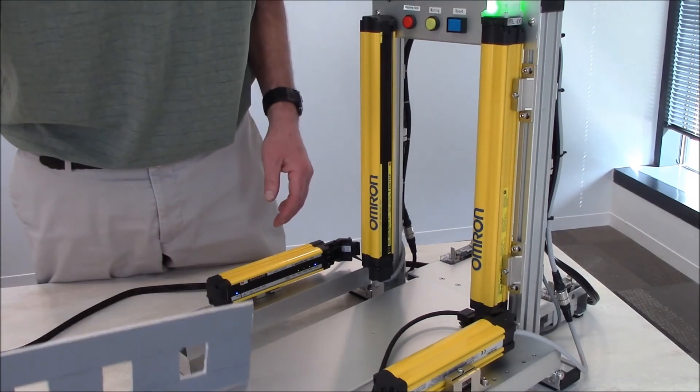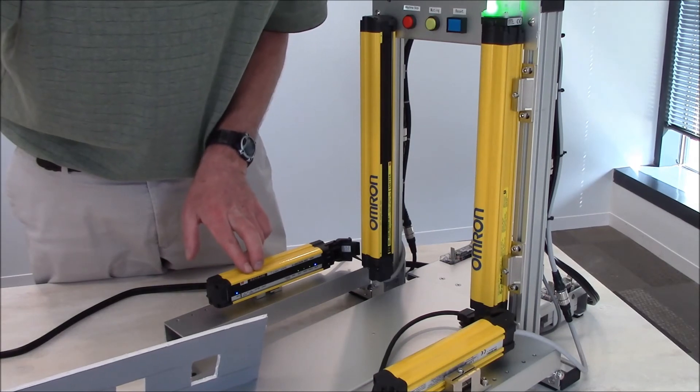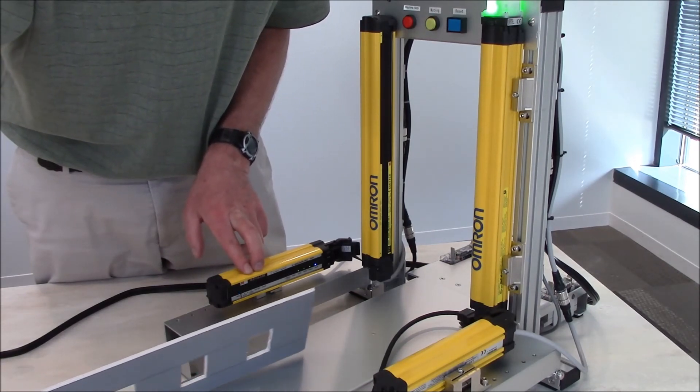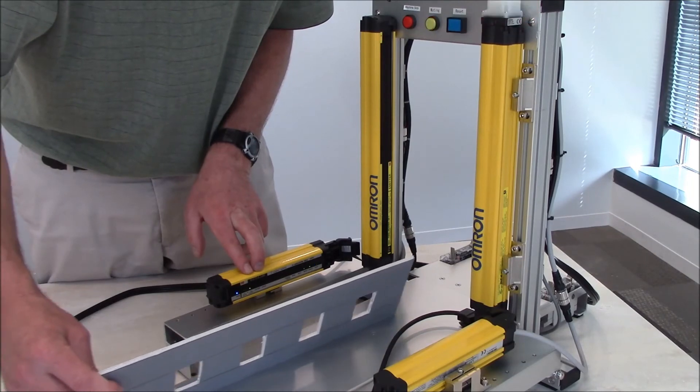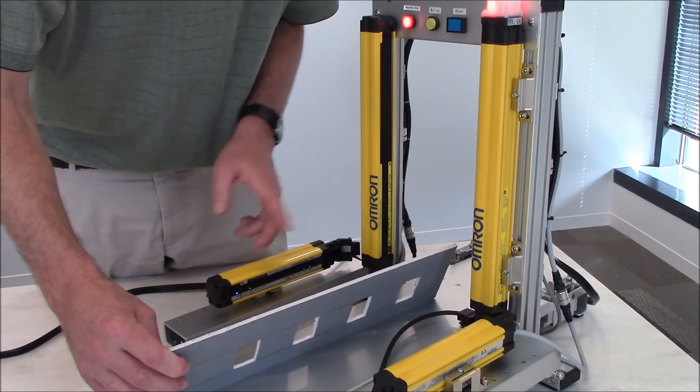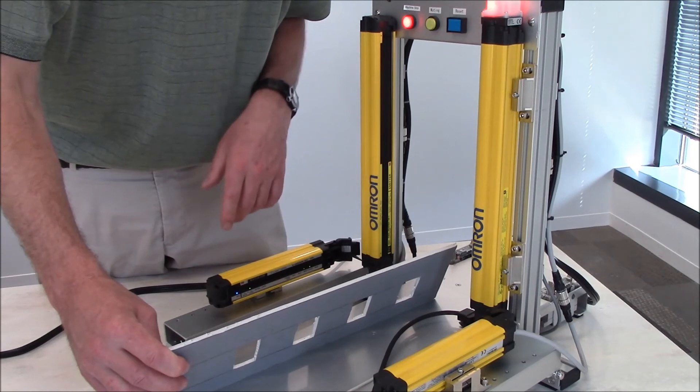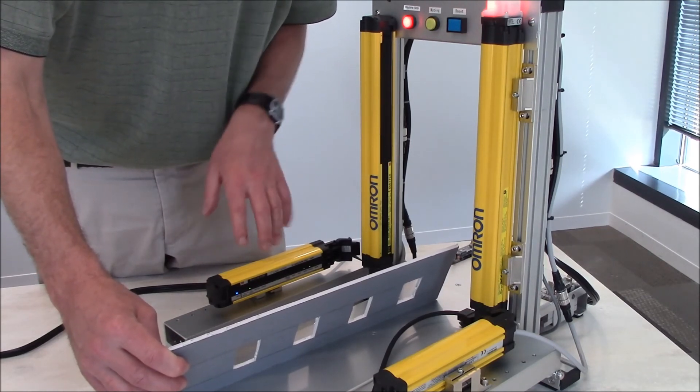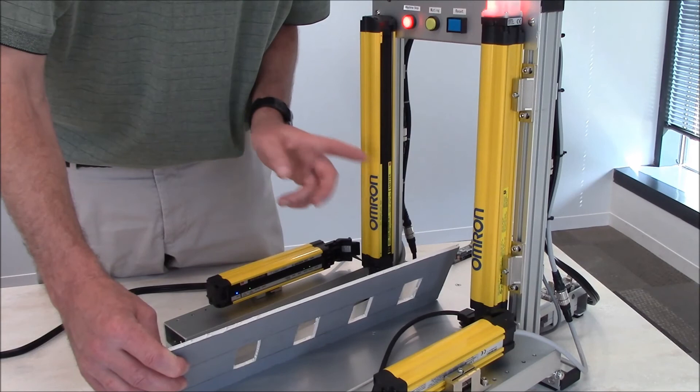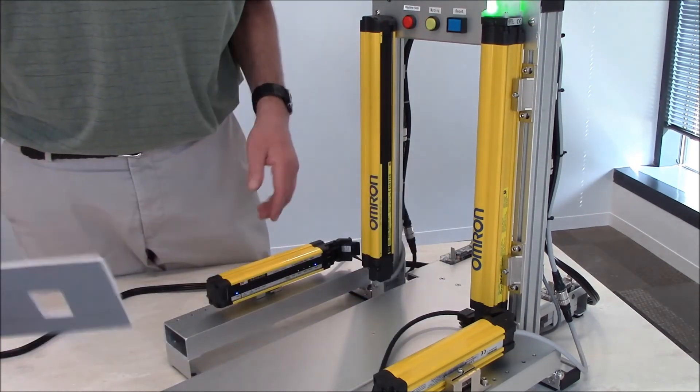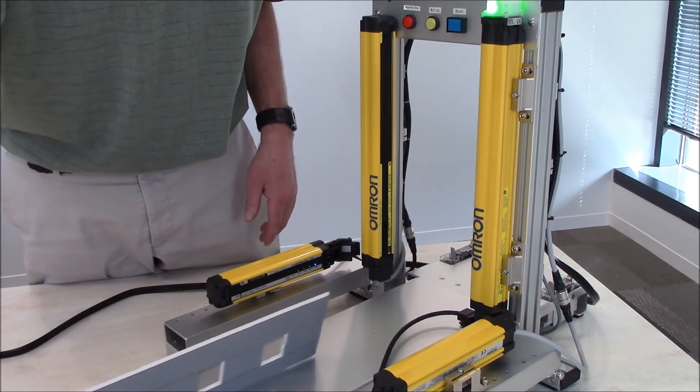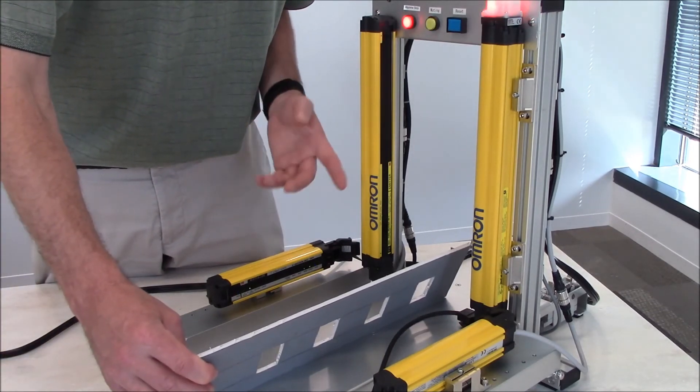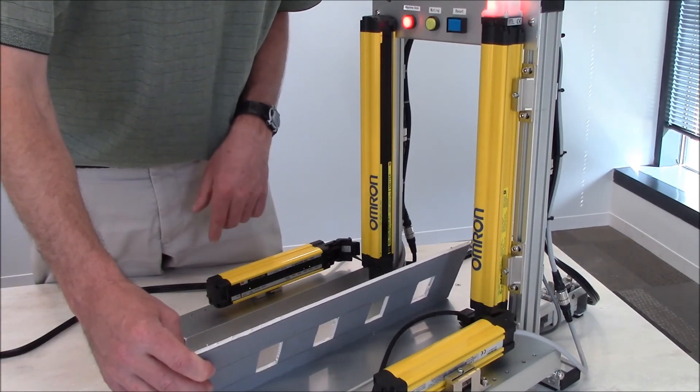If you notice on both sensor A and sensor B, as I come through with the object, you'll see them turning on and turning off. Right as the object enters the muting field, it trips the light curtain because it didn't get the correct timing to satisfy the light curtain. I'll put it through one more time and immediately, boom, because it's turning on and turning off.